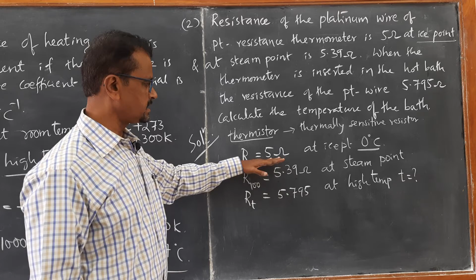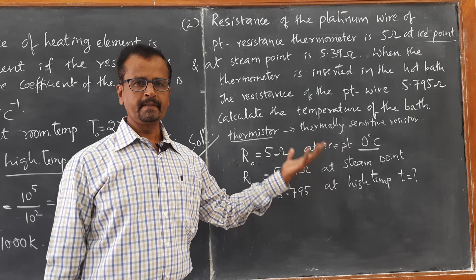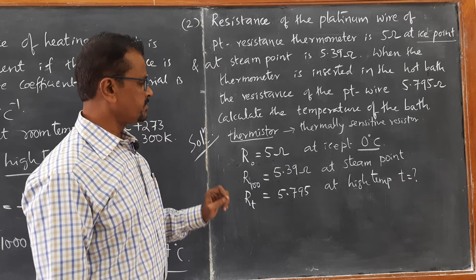So first there are three references here. At ice point it is 5 ohm, at 100 degrees Celsius it is 5.39 ohm, at the higher temperature of the hot bath it is showing 5.795. It means as temperature is increasing, resistance of the platinum wire is increasing. This is the principle of the platinum wire thermometer, that is, thermally sensitive resistor. As temperature increases, resistance increases, as we have studied in the temperature dependence of resistivity of metals. As temperature increases, resistivity increases, so also the resistance increases. So using these standard values, we can find out what is that temperature T.